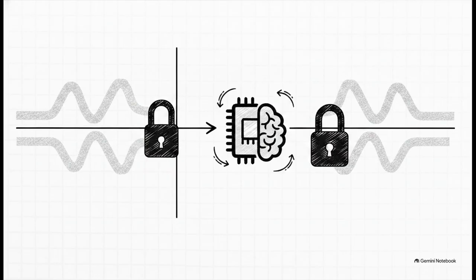But here's the catch: having 2 different sensors is totally useless if their data isn't perfectly aligned in time. Enter the hardware synchronous latch. The main MCU has dual independent analog-to-digital converters, and it forces them to capture these redundant signals in the exact same microsecond window. You might be wondering, does a microsecond really matter? Absolutely. At high speeds, even a millisecond gap means missing huge chunks of energy data. By locking these readings together, the system eliminates the calculation drift that would happen if the timestamps were even slightly off.